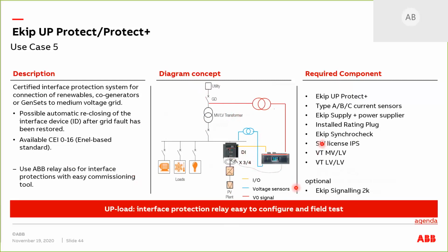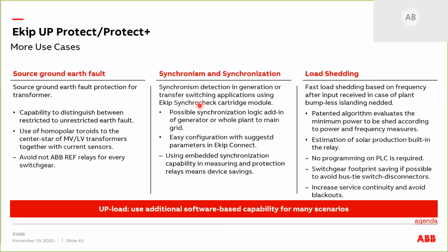Okay, so the EKIP synchro check here is actually checking the synchronization of the voltage and the phase current. This would be a function for the interface protection unit for the medium voltage to low voltage system, just like the embedded IPS system that is in the MCCBs and the ACBs. There are more of this stuff that we can do: synchronism or synchronization, and then the load shedding.